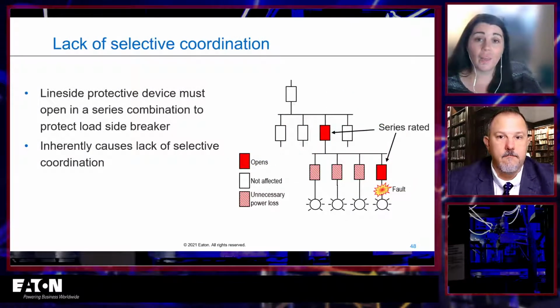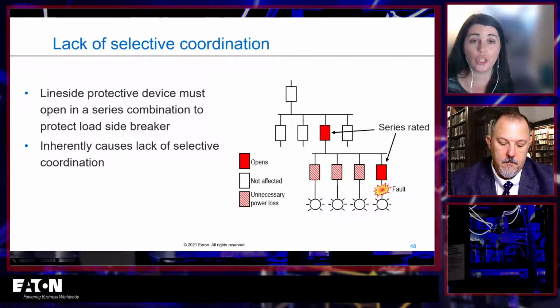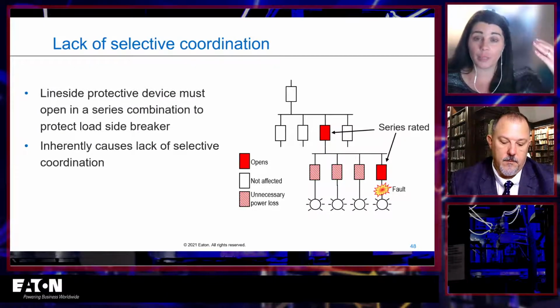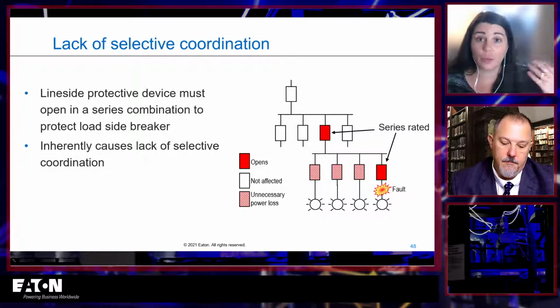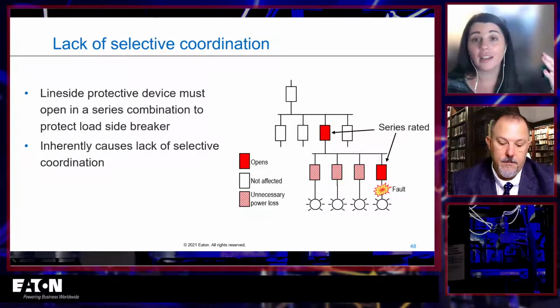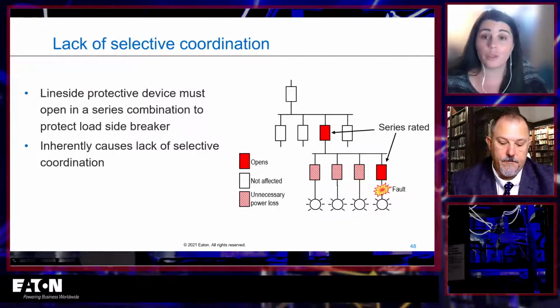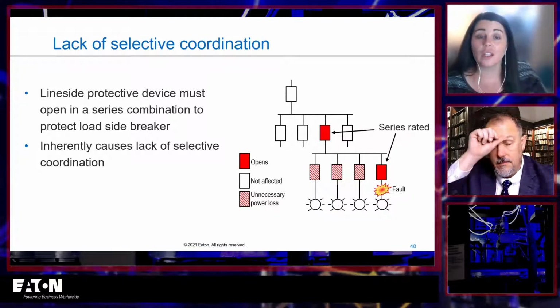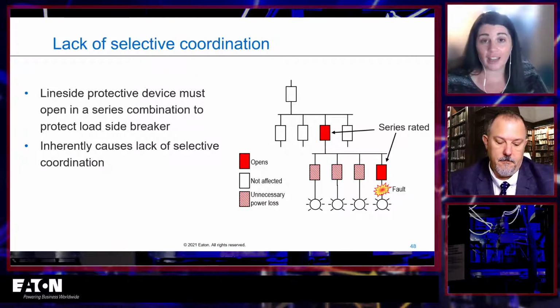And another really big thing is that you lose selective coordination when you series rate. The whole idea with a series rating is that the upstream overcurrent protection device protects the downstream device. So during a short circuit, that upstream device opens. That is inherently not selectively coordinated. And for those who don't know what selective coordination means, it means that you don't have more than one overcurrent protective device open during an overcurrent. The idea being you get a blackout, you get unnecessary loss of power to other circuits whenever that occurs. So inherently, lack of selective coordination.